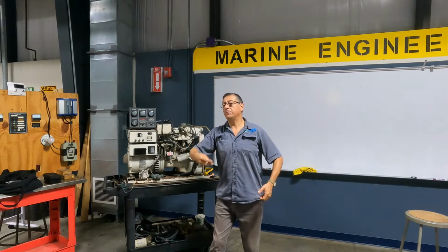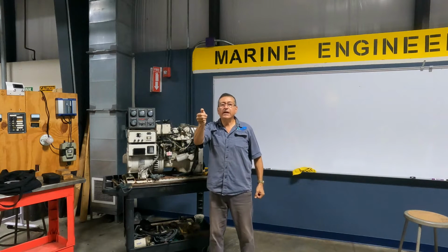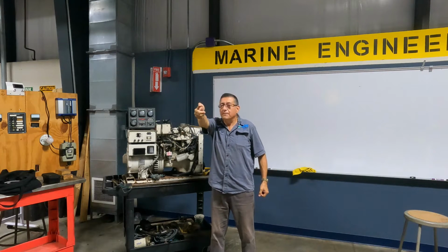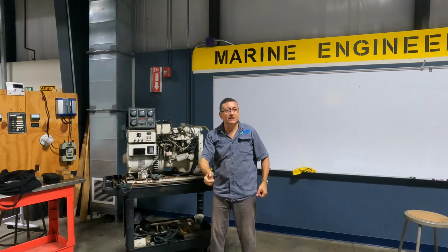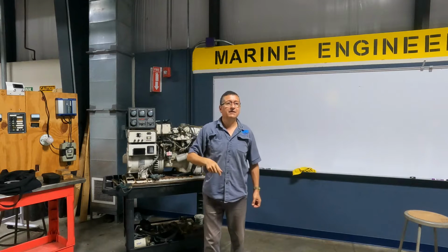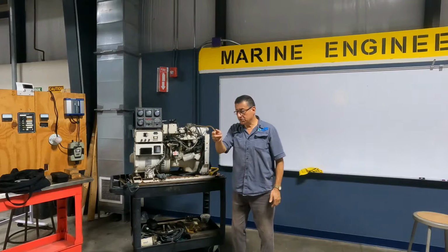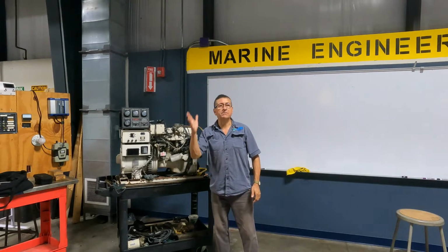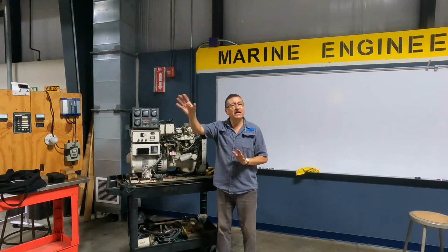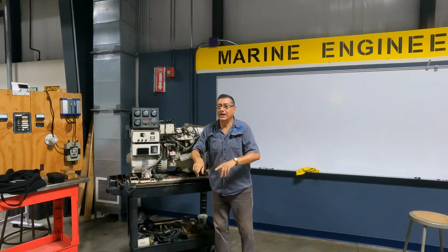That transformer supplies power, and if you open the cabinet doors, you see big breakers for pedestal 1, pedestal 2, pedestal 3, pedestal 4, yeah? I have a problem in pedestal 17. I open the cabinet at the beginning of the dock and I check, oh yeah, the breaker is popped. I have a problem on that pedestal, or on the cable, or on the boat, a short, and the breaker trips.